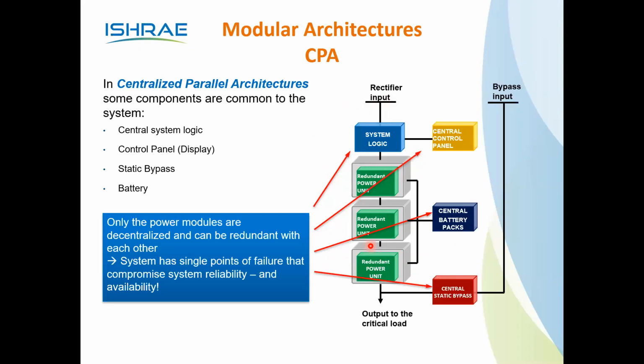This is called the master-slave configuration. This is nothing else; it's a master-slave configuration. This is the master, and the rest are all slaves. If a slave fails, not a problem. The master will control the other modules to support the load. But if the master fails, everything will go off. It's called a centralized parallel architecture. In another way, we can say it's a semi-modular UPS architecture.